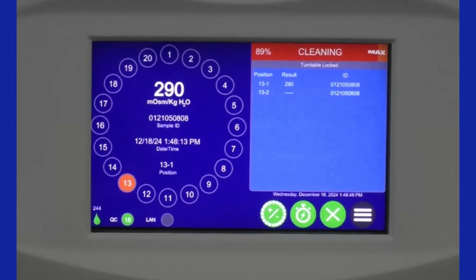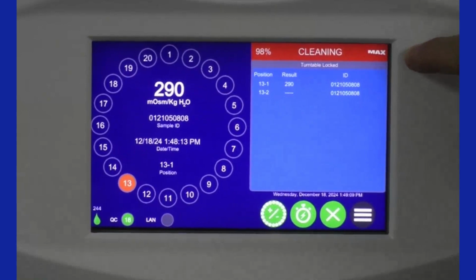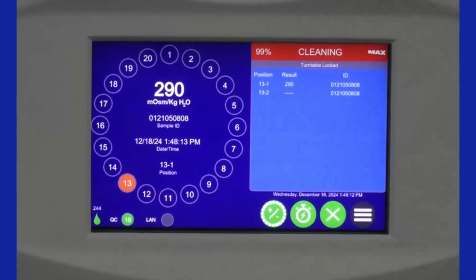Okay, so I completed the first test. We're right on the money. All I did was take some of that 290 and put it into that sample tube. So we're right on the money with the results, so that's wonderful. You can see over here that in position 13-1, we have our 290 result. And because I programmed it to run everything in duplicate, it automatically just goes right into cleaning. Once it's finished cleaning, it's just going to go right back into that tube, take up another 480 microliters, retest, report that result, and then move on to the next sample in the queue, if I had more than one sample. In this case, I don't.